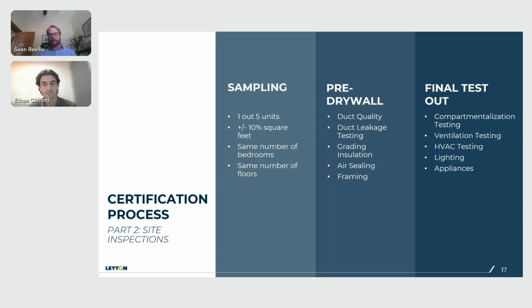We're also going to be doing ventilation testing. So all units have to meet ASHRAE 62.2 to qualify for Energy Star. In addition to that, kitchen fans and bath fans have to have minimum flow ratings and exhaust that air to the outside. So we'll be testing both of those. HVAC testing is actually going to be done by a third entity, which is going to be a functional testing agent. It's either somebody who's a very well credentialed HVAC technician or a professional engineer. Then finally, we're going to be looking at lighting for LEDs and at appliances just to see how efficient they are.